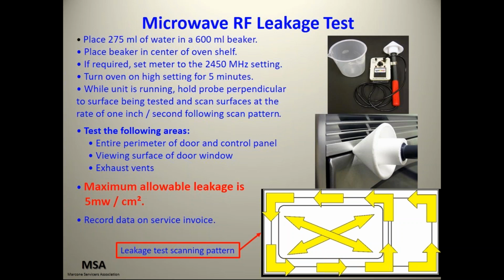Following the scan pattern, you want to test the following areas: the entire perimeter of the door and the control panel, the viewing surface of the door window, and the exhaust vents, and you see these arrows here. Maximum allowable leakage is 5 milliwatts per centimeter squared. You want to record that data on the service invoice.